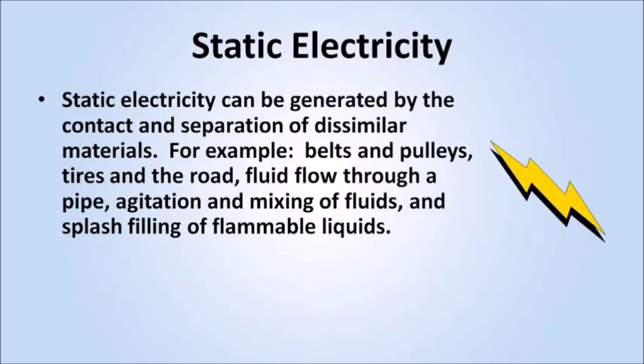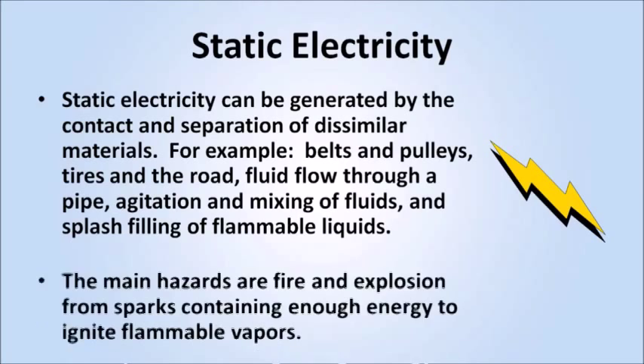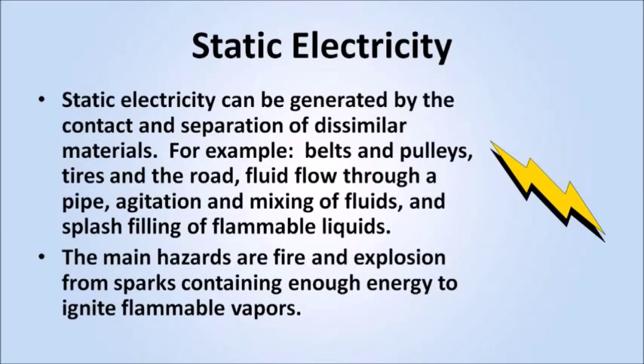Static electricity can be generated by the contact and separation of dissimilar materials. For example, belts and pulleys, tires and the road, fluid flow through a pipe, agitation and mixing of fluids, and splash filling of flammable liquids. The main hazards are fire and explosion from sparks containing enough energy to ignite flammable vapors.